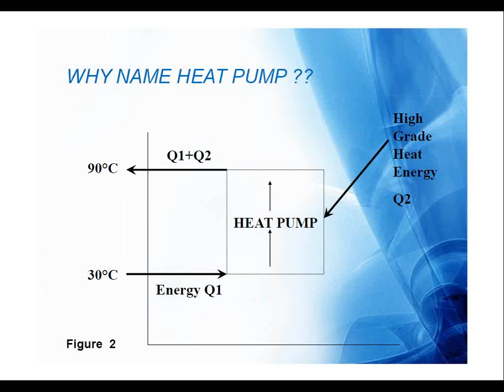So this is a typical presentation of a heat pump, where there are three streams. One is your application stream, which is generating water at a high temperature from low temperature. This application can be used for juice heating itself or for the feed water heating of the boiler water itself. The other stream is the waste stream, which is typically available in all the sugar industry, which is cooling water heat. The cooling water heat is getting dumped into the cooling tower. For example, say 38-degree water is getting dumped into the cooling tower, and the cooling tower is supposed to bring it back to 32-degree, so that this cooling water will be used in the process or the condenser of a power plant or for the electrical chiller or the vapor absorption machine.